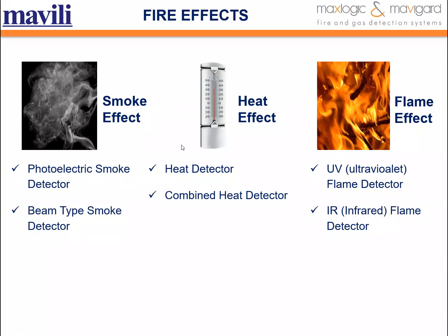In the occurrences of fires, the order of the information of the effects of fire may vary depending on the characteristic of the flammable materials in the area. For example, since in the fire of wood or cotton, first of all smoke occurs, the temperature increases, and lastly, flame is formed. While the fire of flammable liquid first increases the heat and the formation of smoke after the flame is formed. Therefore, it's necessary to determine the types of the substances that can be burned in possible fire in environment and their effects in case of fire.